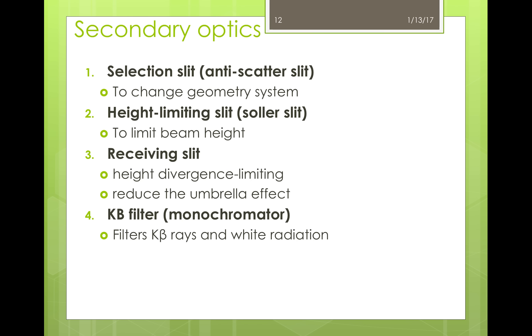Let's take a look at the secondary optics. The secondary optics are on the receiving end of the X-rays that were diffracted by the sample and can be broken down into four main parts. The selection slit, known as an anti-scatter slit, reduces the diffusion or scattering of the X-rays that occurs due to amorphous or air scattering. The height limiting slit, which is a type of Soller slit, reduces the axial divergence and limits the beam height. The receiving slit is the height-divergence-limiting slit that removes diffuse scattered X-rays from previous elements in the secondary optics. Lastly, the beam passes through another monochromator, which absorbs K-beta radiation and white radiation while allowing only K-alpha-1 and K-alpha-2 through.